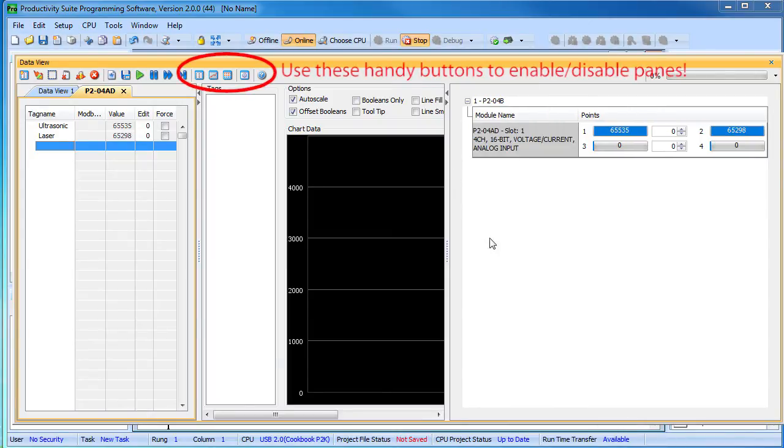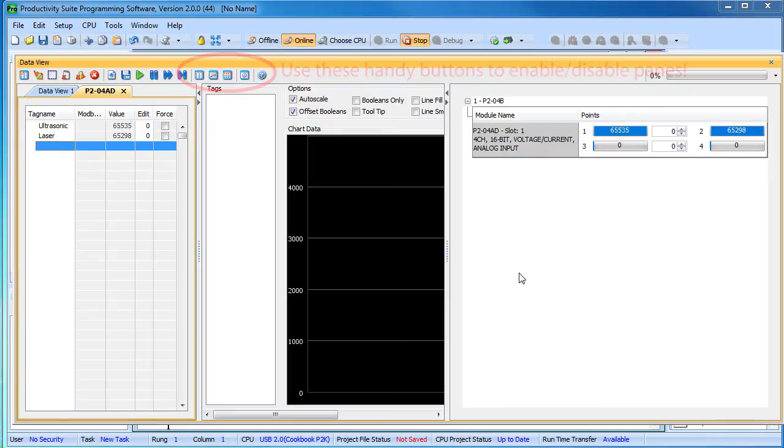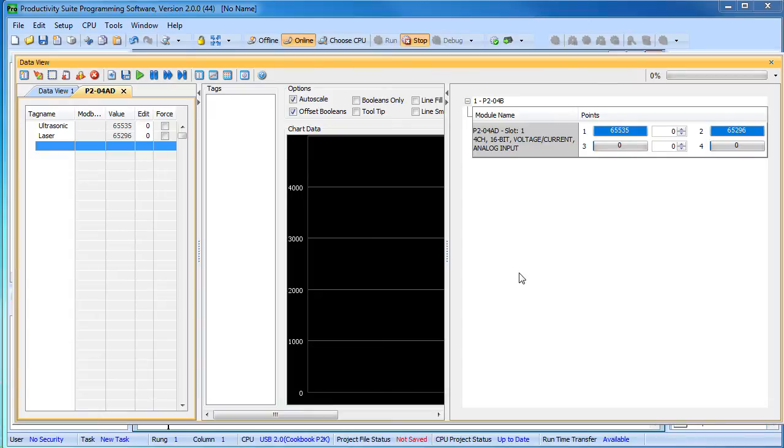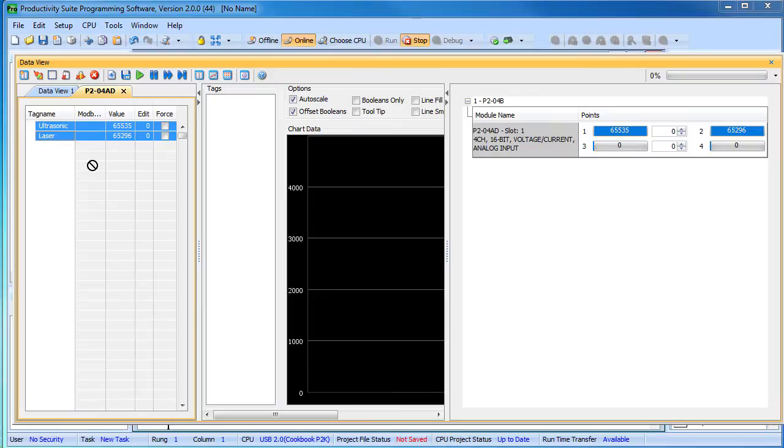You may need to widen the window to see all 4 channels of the analog input module. If I had more modules in this system, we would see those listed here too. Looks like both of our sensors are maxed out right now, but if I put my hand in front of the laser sensor, sure enough the IO responds. If we do the same thing for the ultrasonic sensor, again, same result.